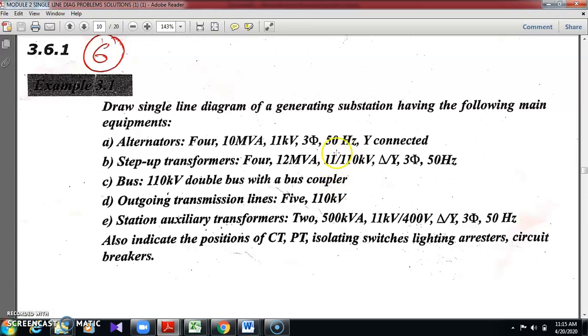Now this is an 11 kV/110 kV substation. Check how many incoming lines and how many outgoing lines there are, and what type of bus bars, low tension and high tension side. 11 kV is low tension, 110 kV is high tension. This is a step up transformer. If the transformer rating is high, then on both sides of the transformer a lightning arrestor has to be given. Understood? Always a lightning arrestor has to be given on the input side, incoming line, either side of the transformer, and outgoing line, if the transformer rating is high and the outgoing line is of high voltage.